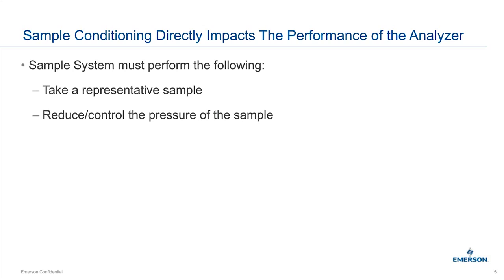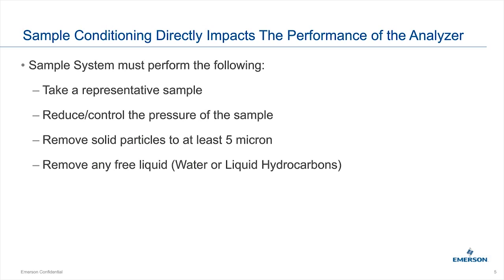It's also important for liquid systems — you may want to maintain or even increase pressure to avoid bubbles forming. Third, remove solids: everything flowing through the pipe picks up contaminants, and the GC doesn't handle that well, so we recommend various types of filters. Fourth, remove any free liquids — the GC operates on clean, dry gas, and anything else can be a very expensive repair. A liquid that is 0.1% of your sample can vaporize at the GC to 600% of the gas volume, completely changing the concentration and making it non-representative of what was in the pipe.